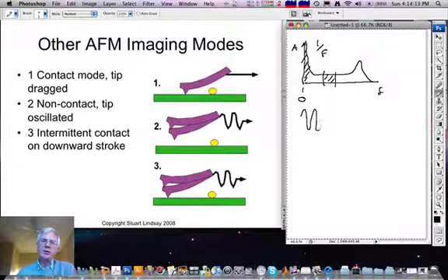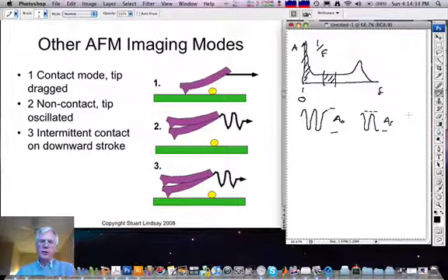at some amplitude A far from the surface. When the probe is brought closer to the surface, the amplitude changes because of long-range interactions between the probe and the surface, and so by making an amplitude set point that is different from the free amplitude, the probe can be operated in non-contact mode. I'll talk about this more in another slide.